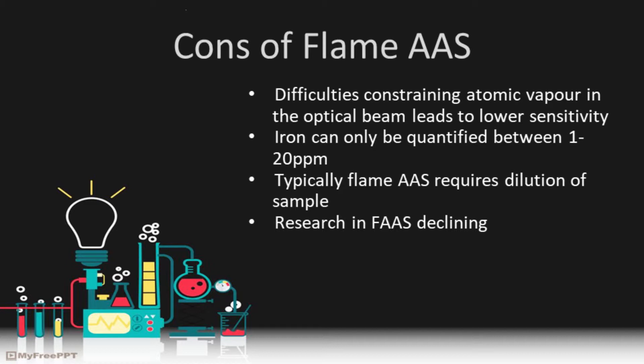The most striking flaw is the difficulty constraining atomic vapor in the optical beam. This leads to lower sensitivities, therefore requiring greater concentrations of iron before detection is possible. There are also limits to the scale on which iron can be quantified, normally requiring a concentration in the order of one to twenty parts per million. This may lead to the need to dilute many samples prior to analysis, which increases the chances of error as well as time and energy preparing samples. Furthermore, few improvements are being actively researched into flame AAS as other more modern instruments are leading the way in analytical analysis of iron and other metals.